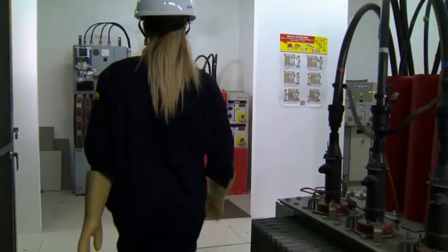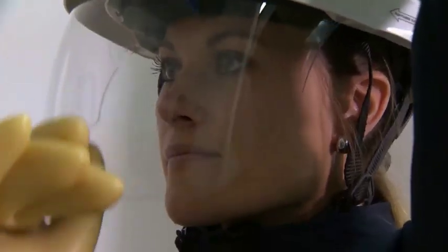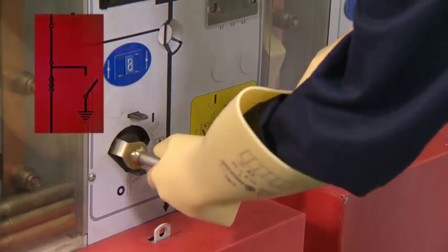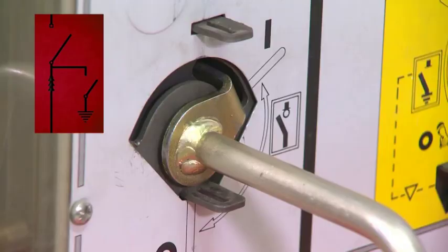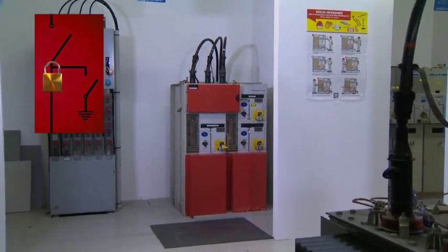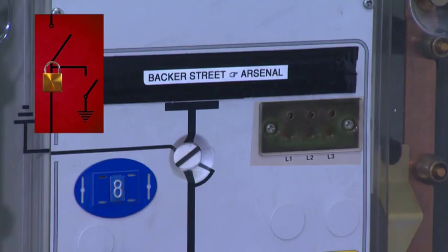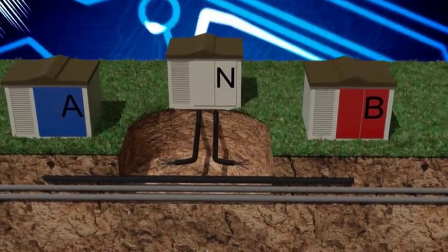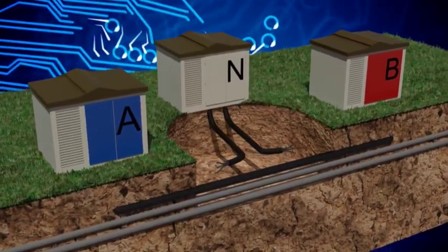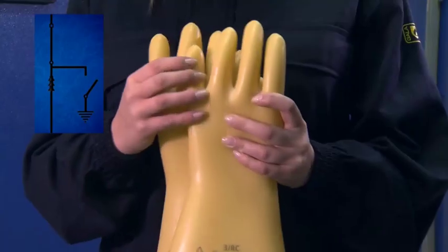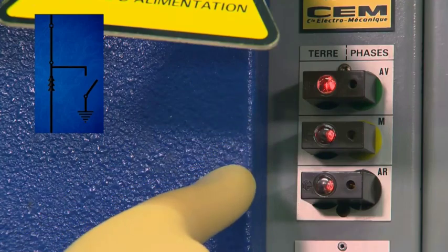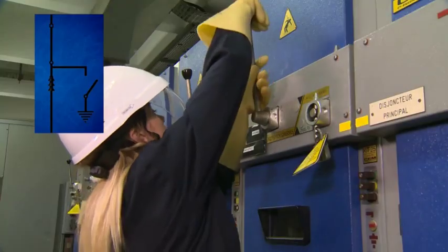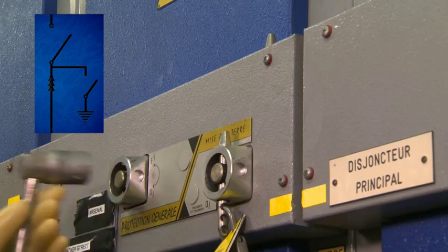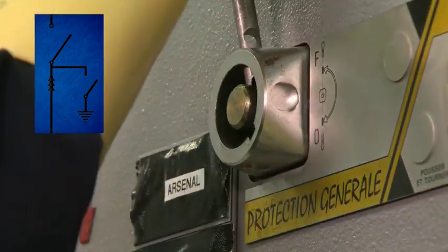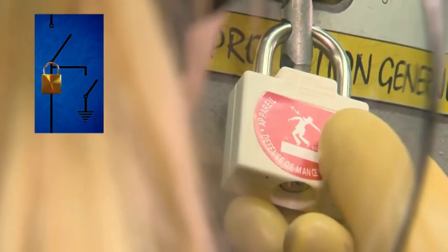Decommissioning operations start with the opening and locking of the switch in substation B, called here Backer Street. The switch for substation B is opened and locked by the decommissioning operator. The cable is now separated on one end, but the cable is still live. The decommissioning operator then repeats this procedure in substation A, called here Arsenal. He's about to open the second switch and to lock it by using one of his decommissioning padlocks. The cable is now isolated from the power sources and locked at both of its ends.